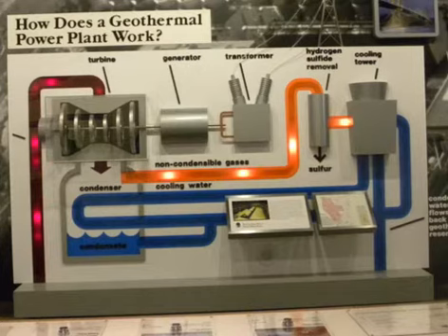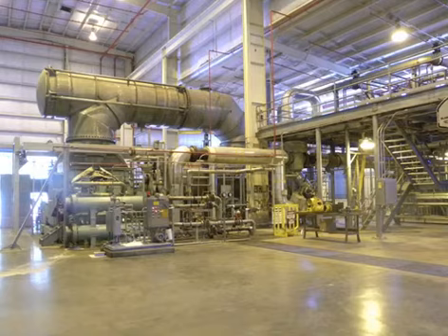This is a model representing how the power plant works. Inside of the West Ford Flat unit, there are 2 turbine generators that each generate 13.5 megawatts, producing a total of 27 megawatts. This unit is supplied by 9 wells that provide 424 kilopounds of steam per hour. The turbine shaft rotates at a rate of 3,600 revolutions per minute, and the inlet pressure of the turbine for the steam is 100 psi.